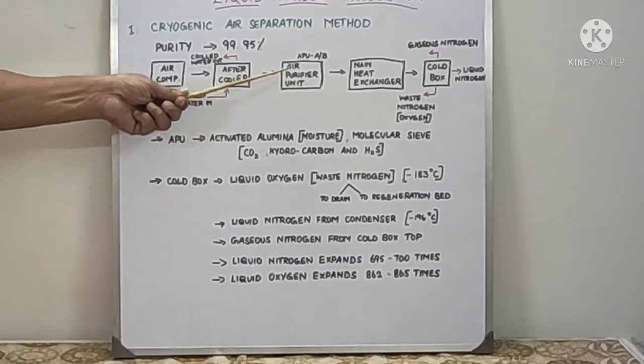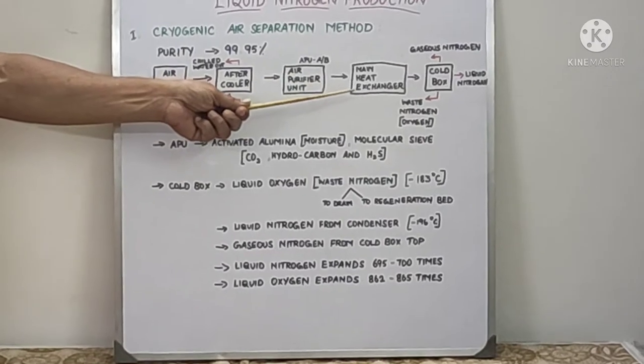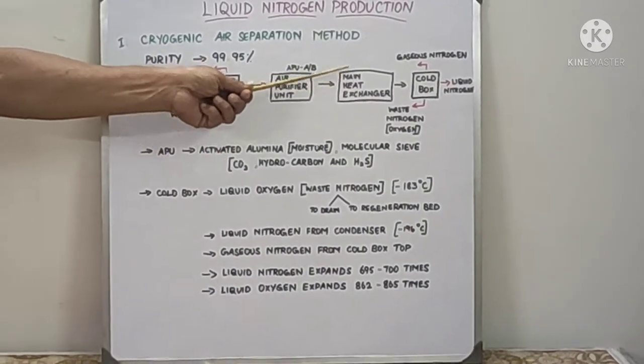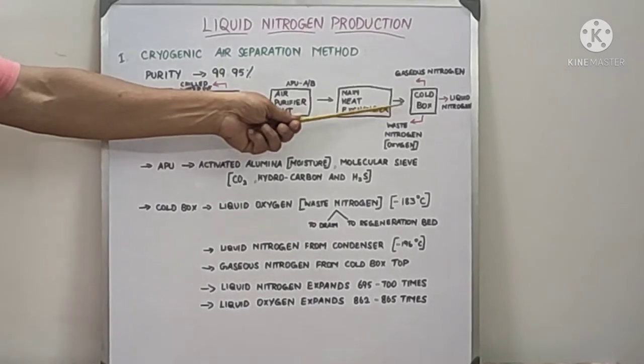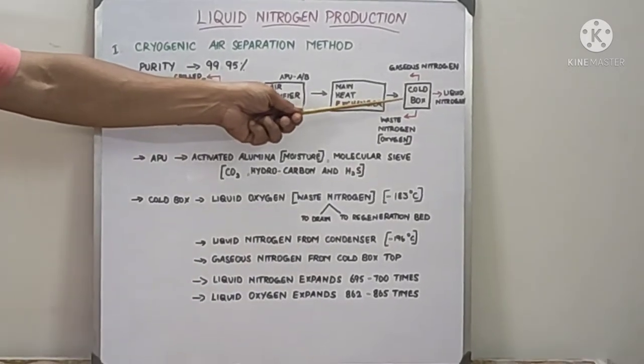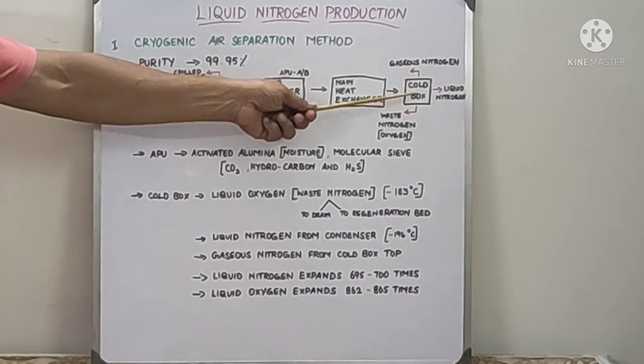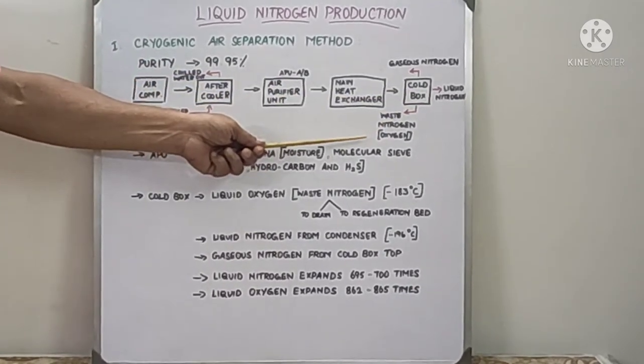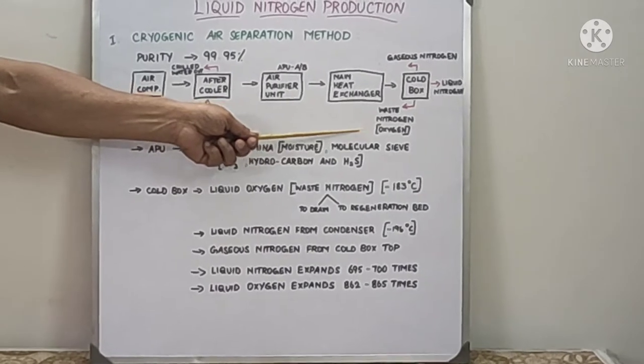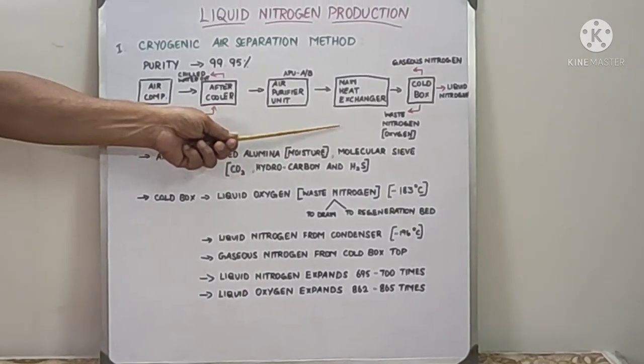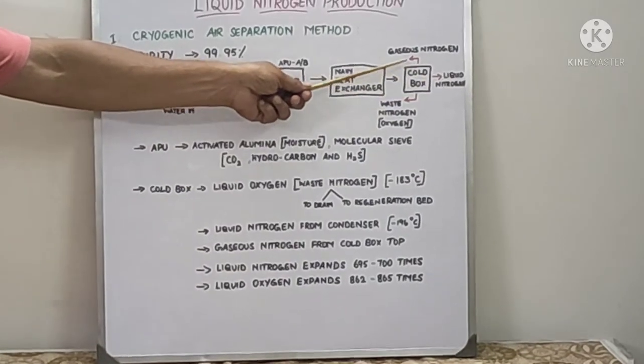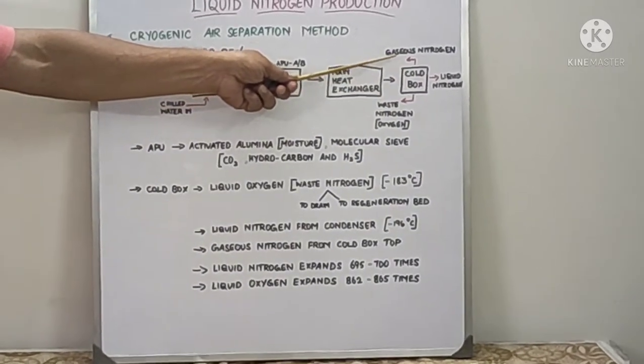After this, the air purifier outlet goes to the cold box via main heat exchanger. In the cold box, we are having two condensers and a high pressure column or rectifier. From there, you will get waste nitrogen or oxygen to vaporizer to drain or vent, and liquid nitrogen as a product. If you need gaseous nitrogen, it will be collected at the top.